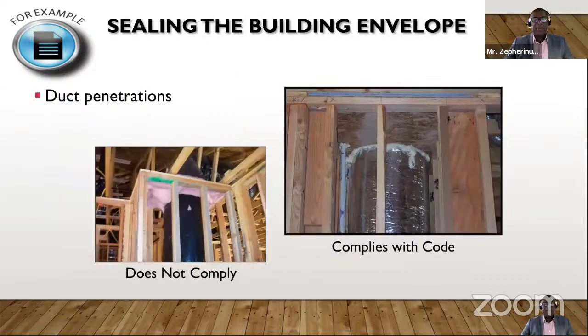Another example here, as far as the duct penetration, the duct penetrations must be properly sealed. And you can see an example on the left that is not code compliant, and the example on the right where the duct is properly sealed, separating the ceiling or the attic from the conditioned space. So around the duct, you can notice that there's some sealant to prevent air leakage through between the duct and the ceiling.